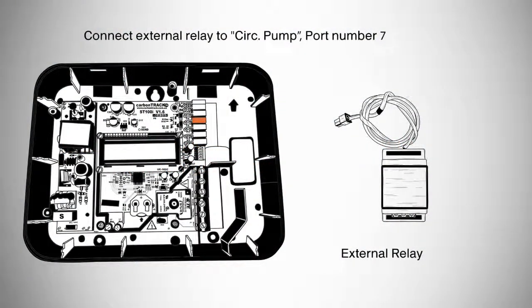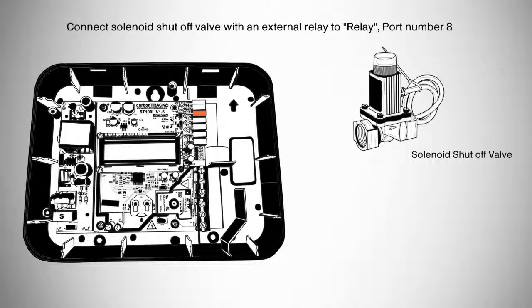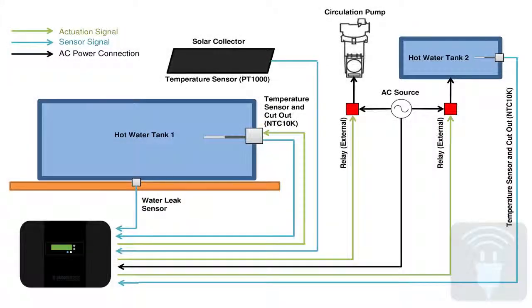The next step is to route the wire between the ST100i and the electrical points, primary geyser, and circulation pump. An external relay will be needed for the circulation pump — connect it to CIRC pump, port number 7. Also connect the additional geyser or solenoid shut off valve with an external relay to relay port number 8. Verify that all connections are proper and in the correct place.